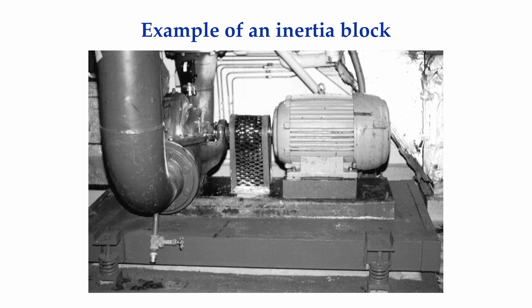Not all rotating machinery is at ground level. Some drive systems are located on the upper floors of buildings. Here is a typical inertia block. A reinforced concrete slab is encased in a steel frame. The inertia block is frequently isolated from the floor on springs. Base plate or sole plates or chock plates are typically bonded to the inertia block using grout, similar to the monolithic foundations reviewed previously.